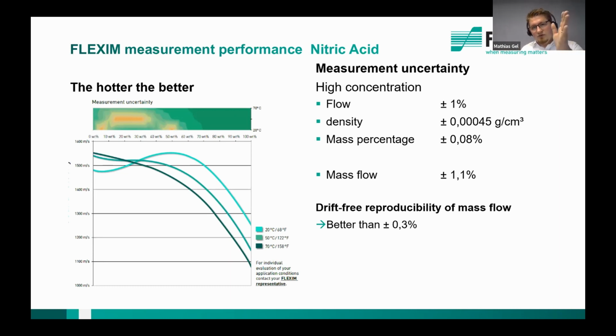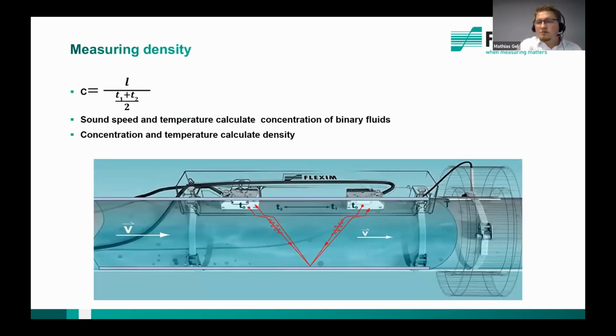Now, with regards to the density measurement, that's a different topic. The instrument will be installed, and then it needs to be one-time field calibrated. Meaning, from your laboratory, or from your supplier, or wherever you get this number, you will tell us one time what we are measuring right now. Is this 90%? Is it 90.5%? So we can set the instrument correctly. The reason is that, as I explained here, we need to calculate L, the distance, and this is very dependent on the exact geometry. It's easier to do it this way around than to measure every tiny part of a millimeter around the pipe. So this has to be done as a field calibration, and then you're good.